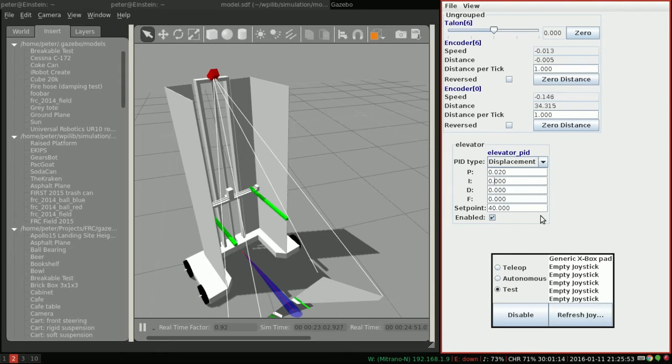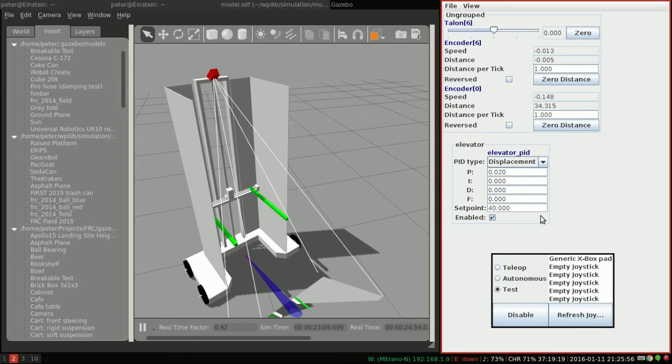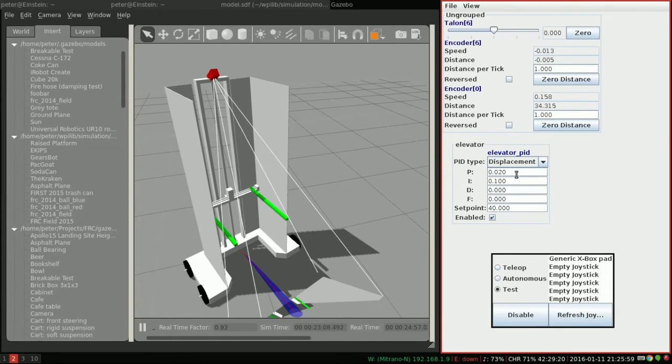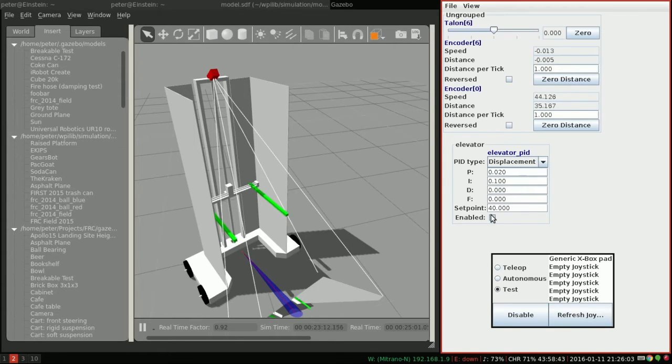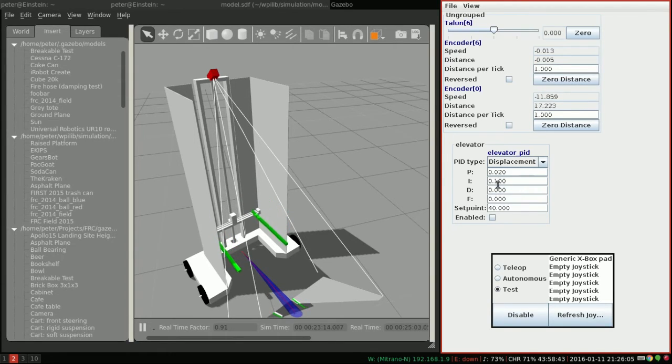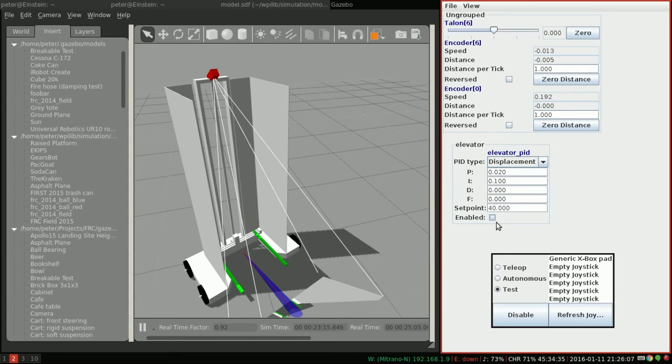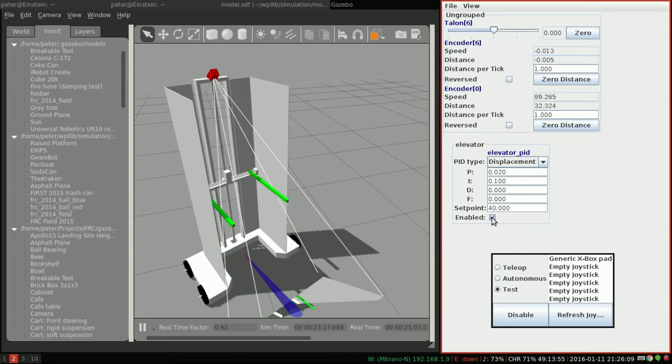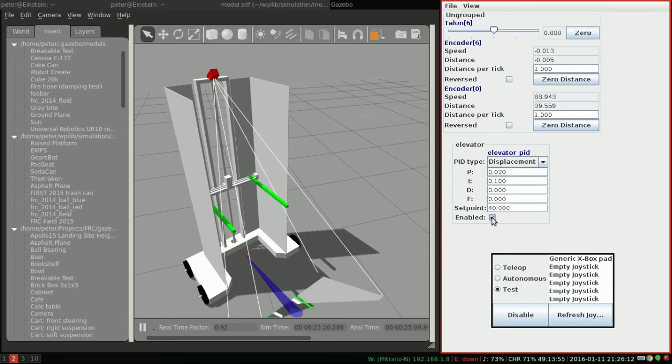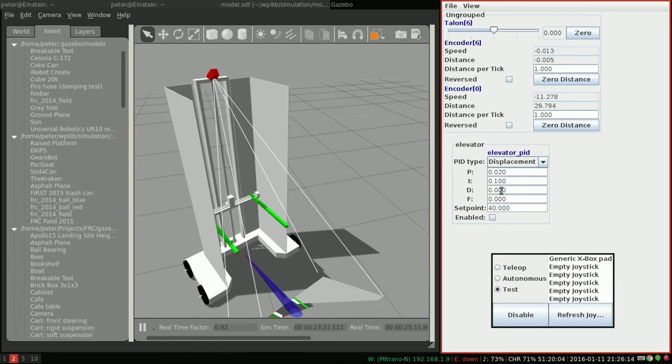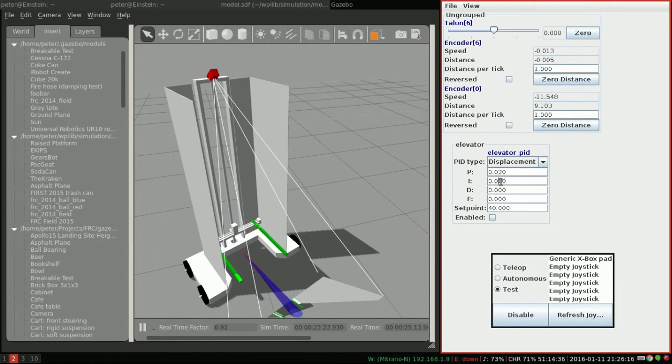Again, we'll start by determining order of magnitude. But in this case, I'm going to start at 0.1 because the I-Term is typically much, much, much smaller than your P or your D-Term. So let's set I, let it go to 0 and enable. You can see we've obviously gone much too far with I. So we're going to decrease it by an order of magnitude and try again.